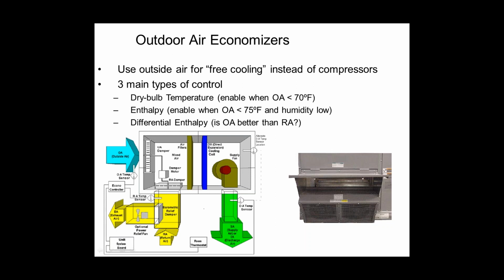For those of you guys that have seen my economizer classes before, you'll notice that over the years that OA less than 70 degrees Fahrenheit number has gone higher and higher every time I do the class. 15 years ago I used to say 55 degrees, and then I got smarter and picked a new number and smarter and picked a new number. And now because of the code, I have to pick 70. Normally, up until last year, I was picking 65, which I thought was pretty aggressive.